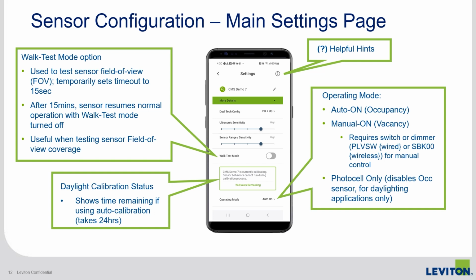Next is manual on, also known as vacancy. In this mode, you'll need to add a switch or dimmer so that the lights can be manually turned on upon entry. The lights will then stay on until the space becomes vacant and the timeout expires. The last mode is photocell only. In this mode, the occupancy detection is turned off and the sensors will only make changes to lighting based on natural ambient light.